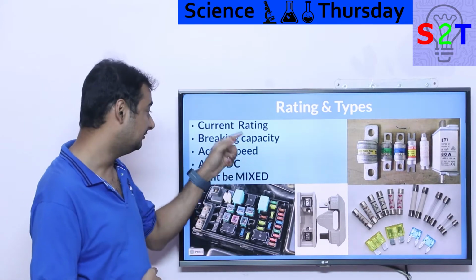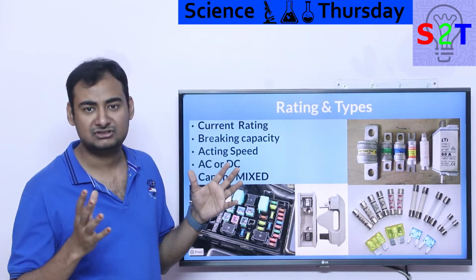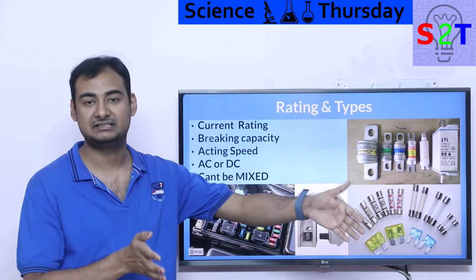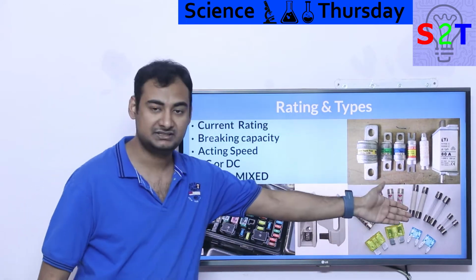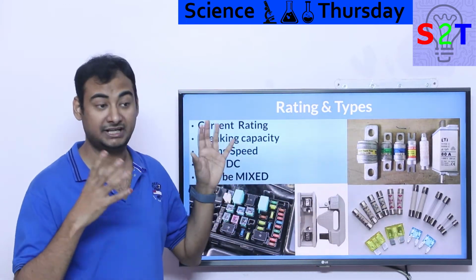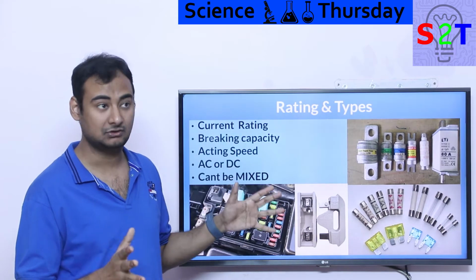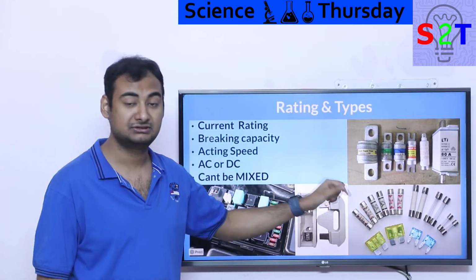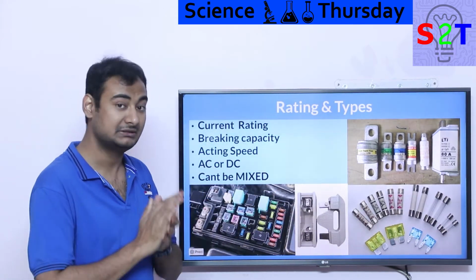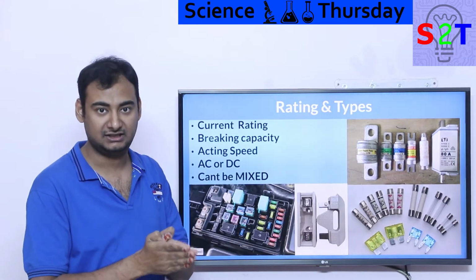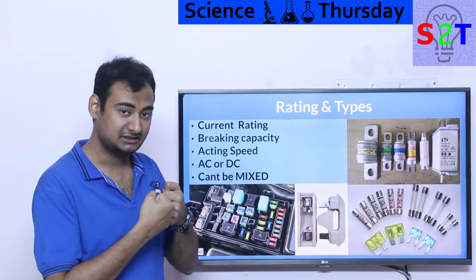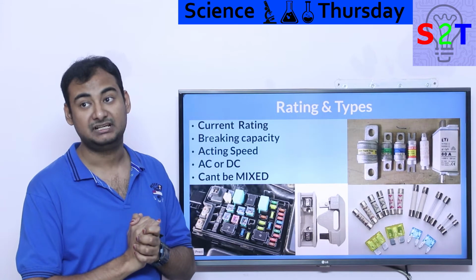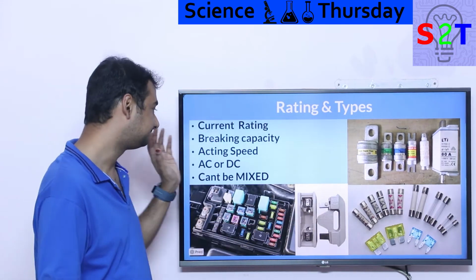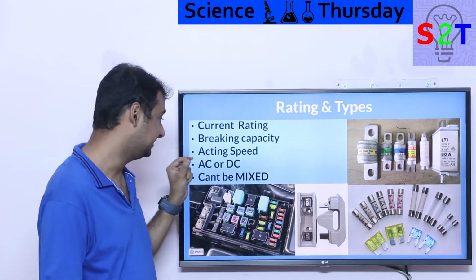That's the whole point of breaking capacity. If you're talking about something simple, like just an extension board, you're going to have a basic fuse. But if you're talking about a serious inductive load that could have a serious fault, you're going to use a sand-filled fuse, because in a worst case scenario with very high fault current, the metal melts and is then extinguished, the arc handled by the sand. So breaking capacity is a very interesting aspect.